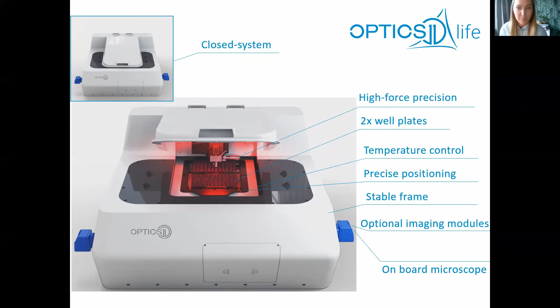The system also has an inverted microscope on board, and it's integrated, meaning that you can just choose in the field of view where you want to measure, and then the probe will just go to that area and measure. That's in contrast to Chiaro, where you have to move everything manually to align the tip with the sample to do the measurements. It also has temperature control on board, so your samples will be happy at 37 degrees. And we have other options for imaging, so fluorescence and confocal, which is on our roadmap and will be launched probably next year, so we can do even more fancy mechanobiology experiments.